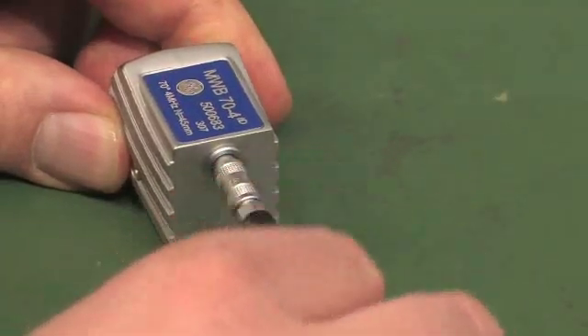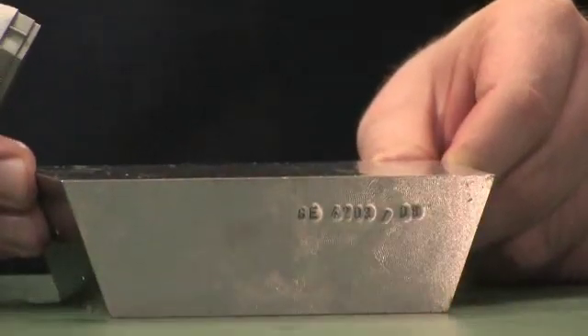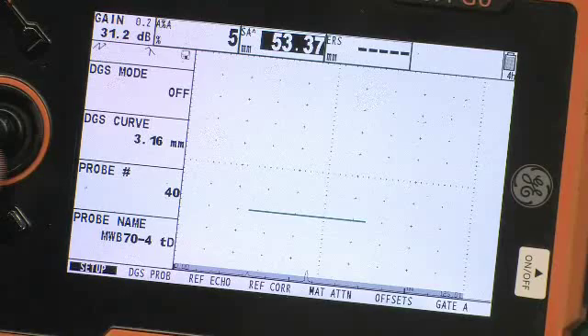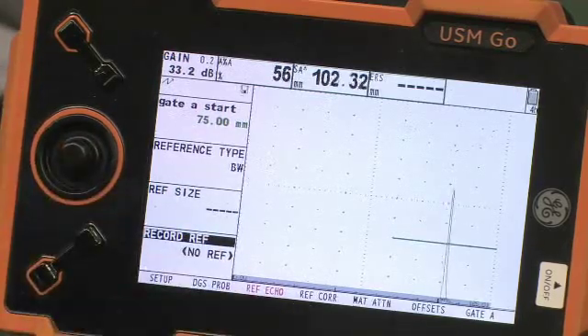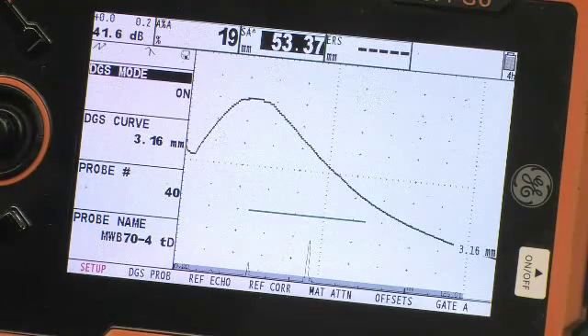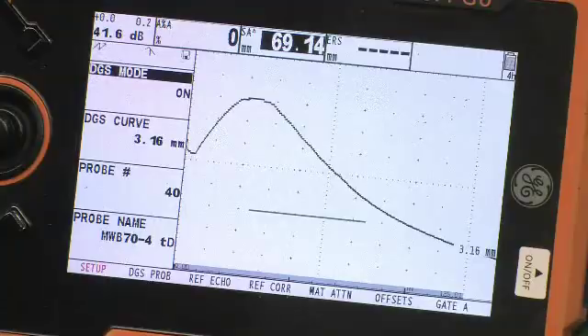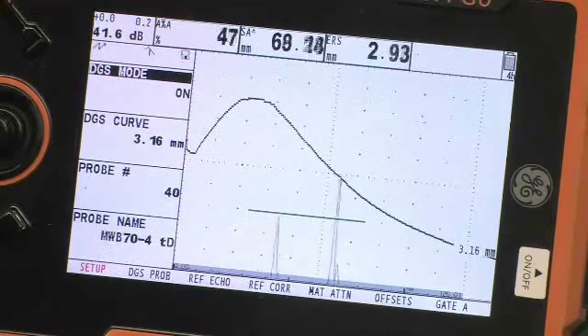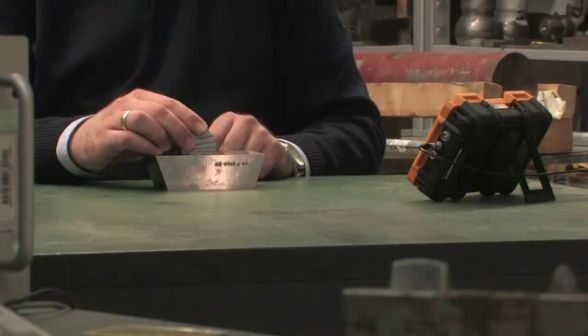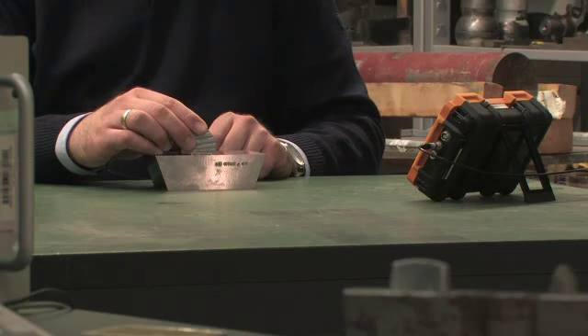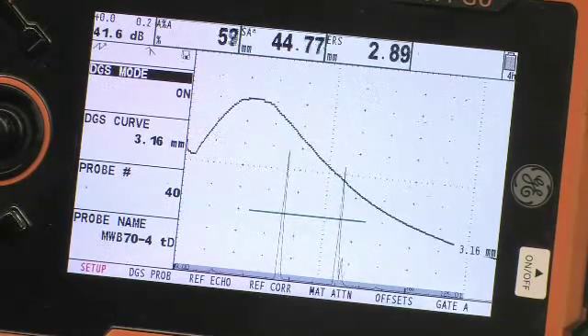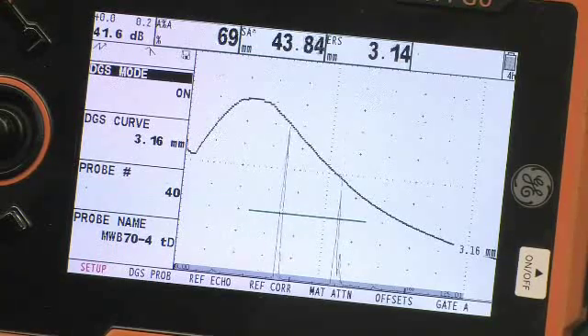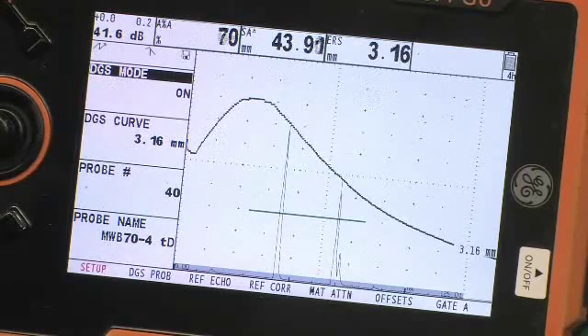The True DGS probes can be used in the same way as MWB, SWB, or WB angle beam probes. Set up the instrument as usual and choose the True DGS probe from the menu. Record the reference echo, switch the DGS mode on, and find the flaw and do the DGS sizing. When comparing the result displayed on the instrument with the diameter measured with a caliper, you can directly see that there is a very good correlation. The newly developed True DGS probes achieve a DGS sizing accuracy superior to those of current angle beam probes with rectangular elements.